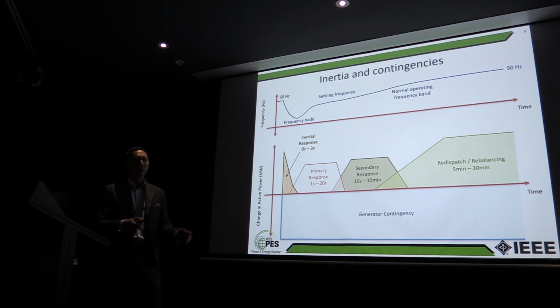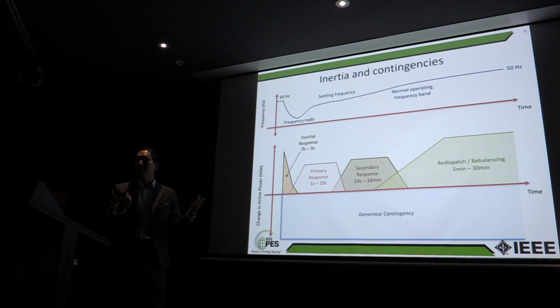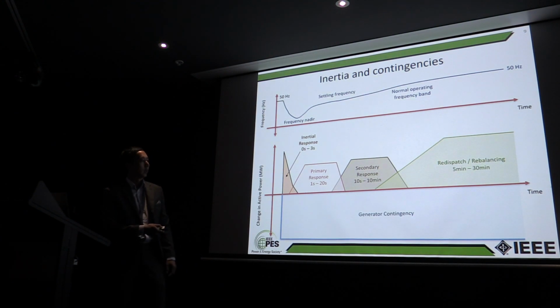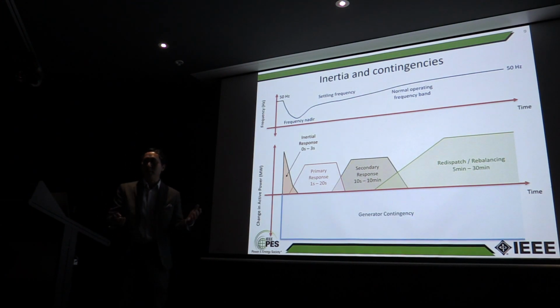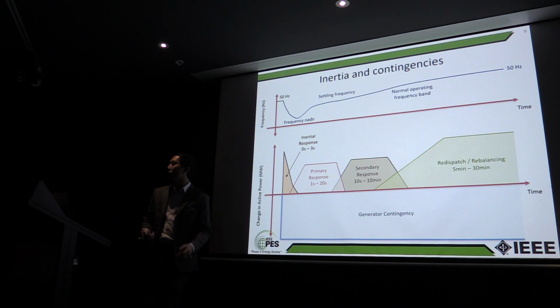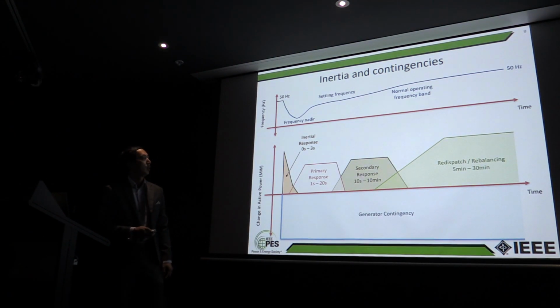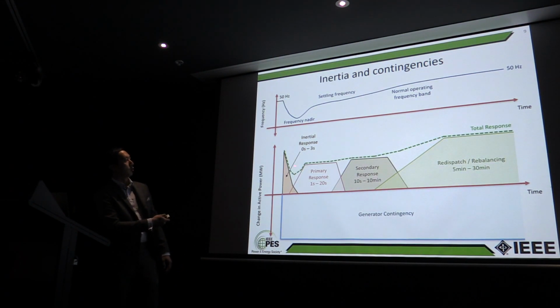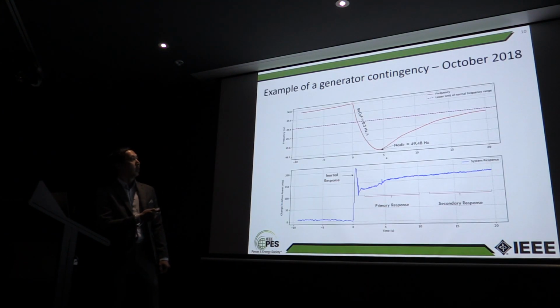You redispatch or rebalance all the other generation, so you basically get all that energy back from rejigging all the generation in the system. So we can draw the total response of the system. And here's a real event. You can see that the response is kind of like that. You have an inertial response, and you have a primary response and some secondary response. I didn't show the balancing because this event was pretty much over in 20 seconds. So these are all automatic.